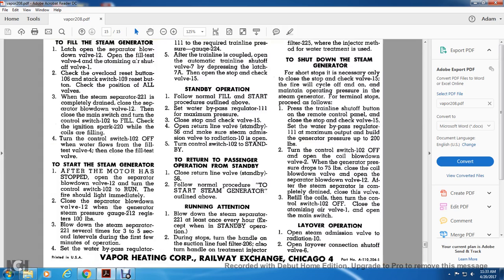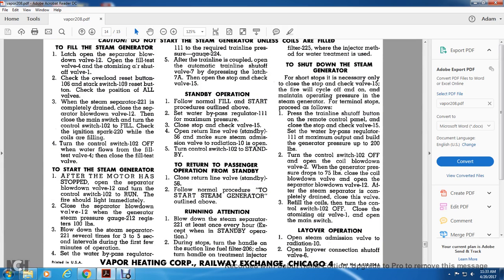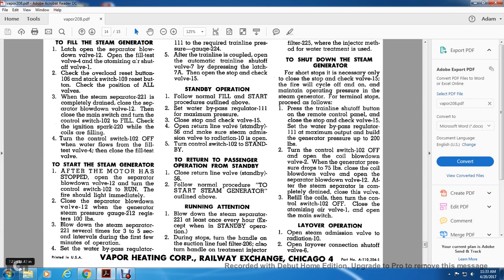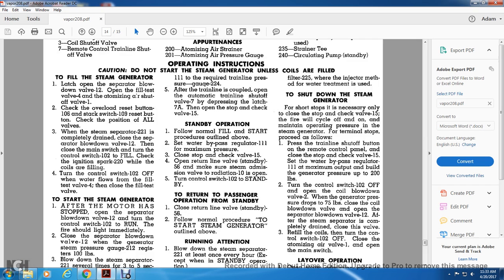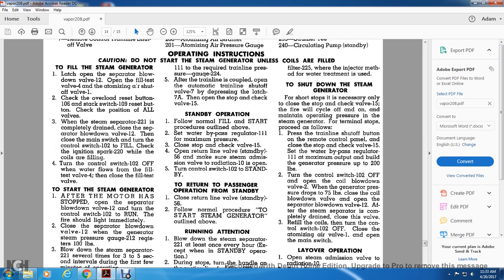To start the steam generator, after the motor has been stopped, open the separator blowdown valve 12 and turn the control switch 102 to run. The fire should start immediately. Close the separator blowdown valve 12 when the generator steam pressure gauge 212 registers 100 pounds. Blow down the steam generator. Blow down the steam separator 221 several times, at 3 to 5 second intervals, during the first few minutes of operation. Set the water bypass regulator valve 111, using the return line pressure gauge at 224.